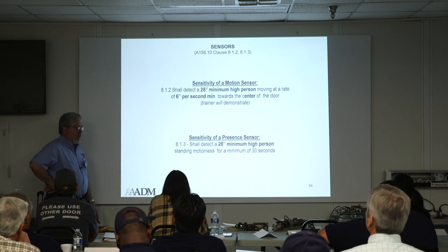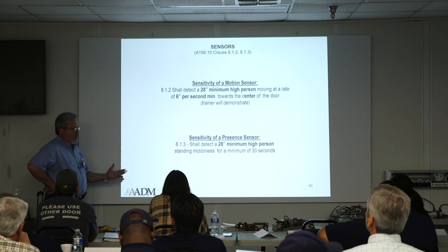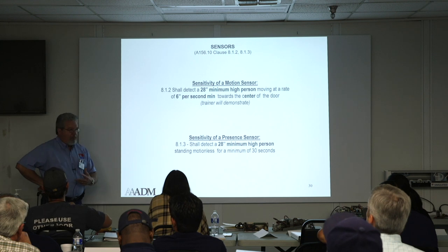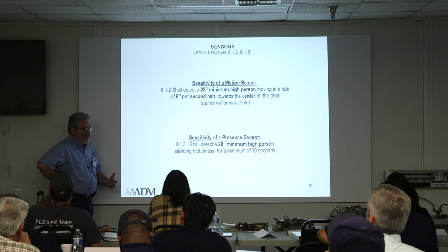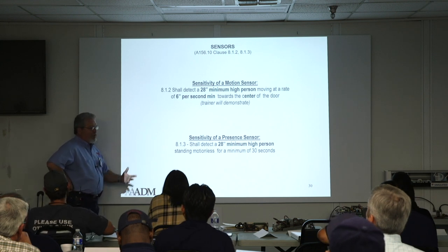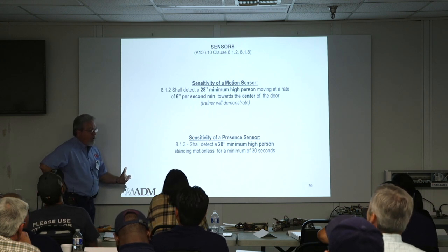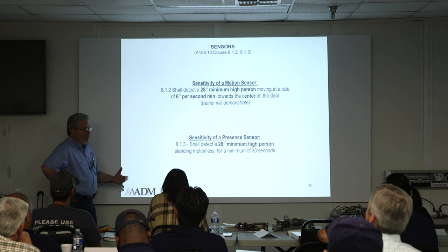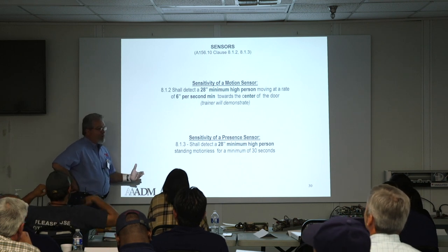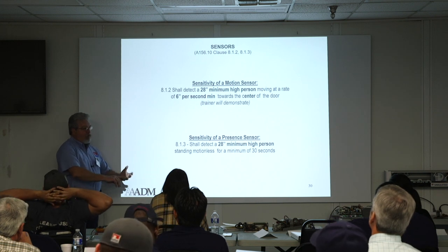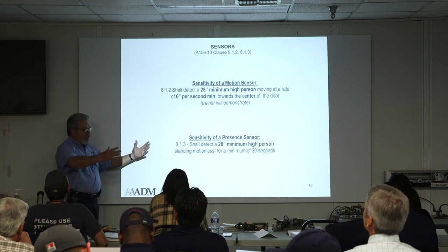Always consider your application. Always consider the traffic that's going to be using that door. If you have an old folks home, I'm probably not politically correct, but anyway, you know, someplace where you're going to have very slow moving, frail people, you want the door to open and close slower. You want the time delays to be longer. You want the detection zones to be bigger.